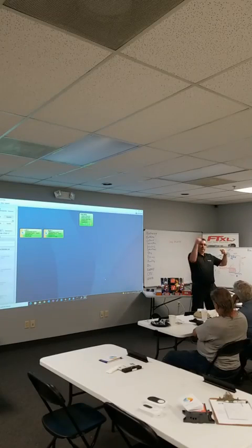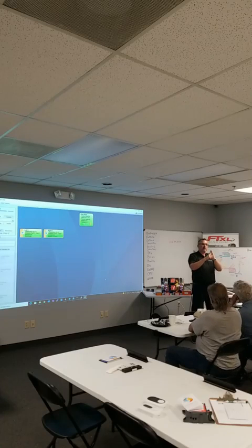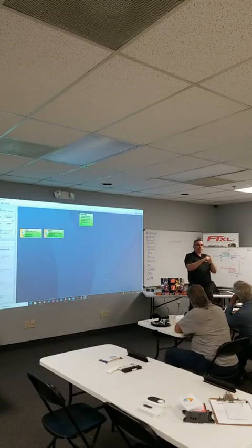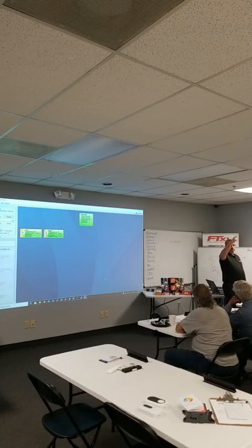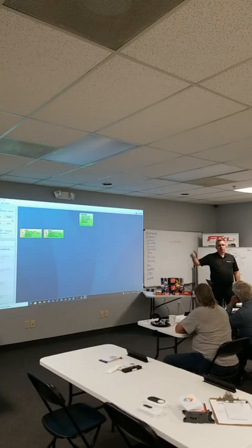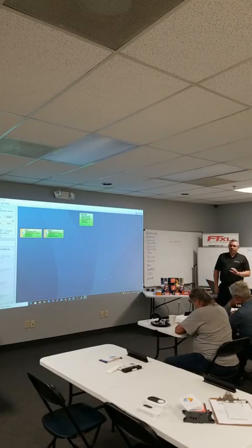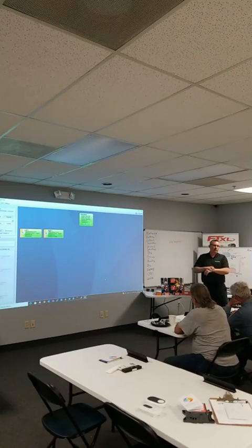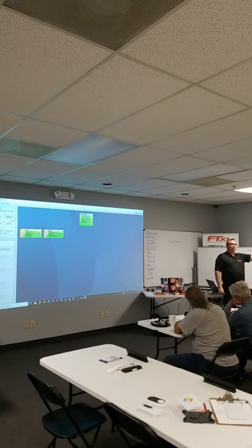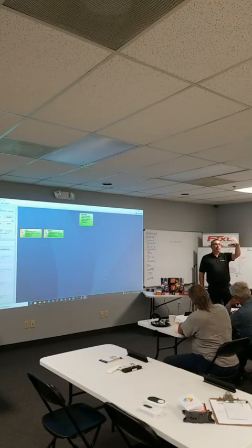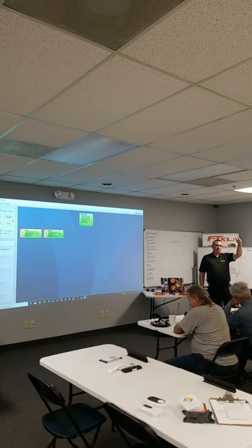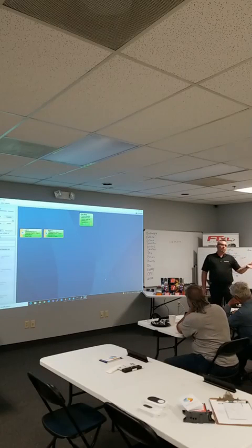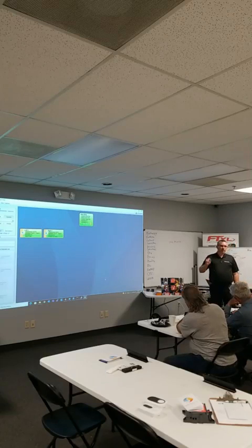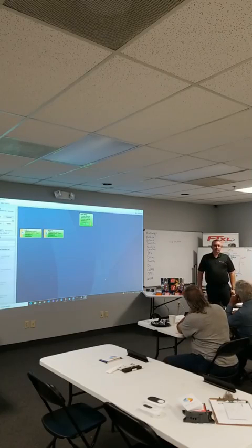So what we did, the compressor had to be calling to run, and the pressure had to be above this, or the pressure had to be below this, and then we would turn on two outputs. And then we alarmed those two outputs. For whatever reason, I don't know why he was so adamant, but that's what we did. So we just looked at the status. Is the compressor being commanded to run? Yes. And is the pressure above this? No, no alarm. Is it above this? Yes, there's an alarm. Is it below this? No. If the compressor wasn't being commanded to run, like if somebody shut the unit off or something, then the controller wouldn't alarm. That tells him, hey, controls or.